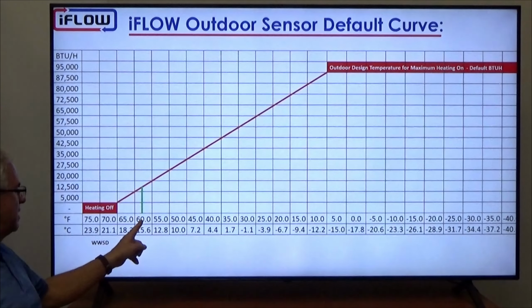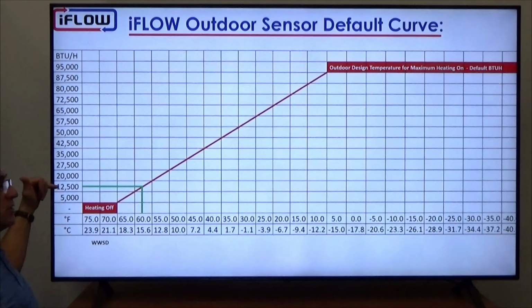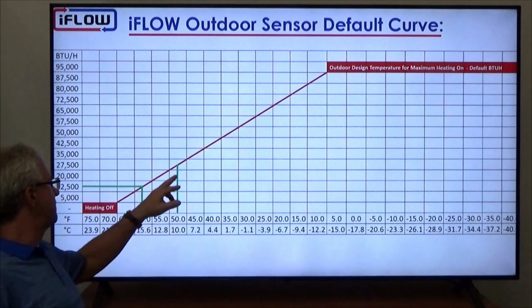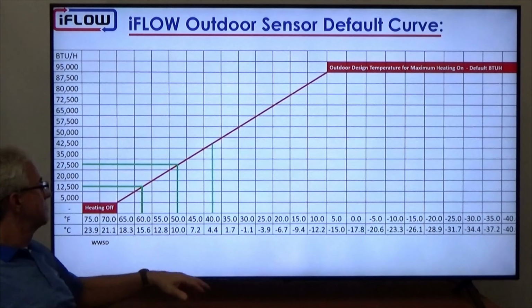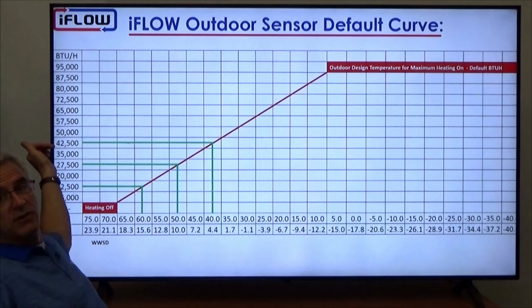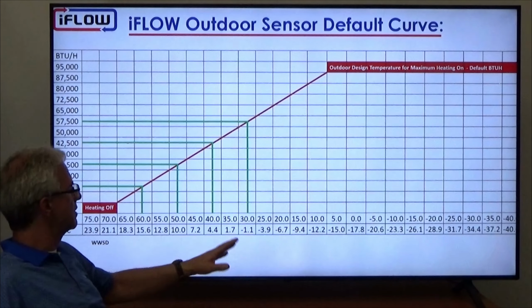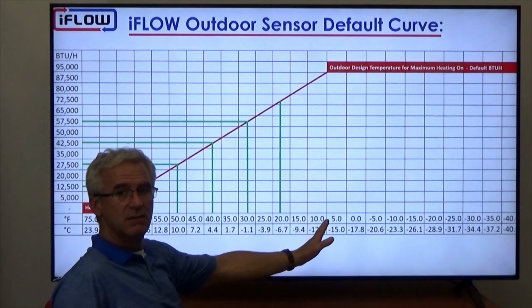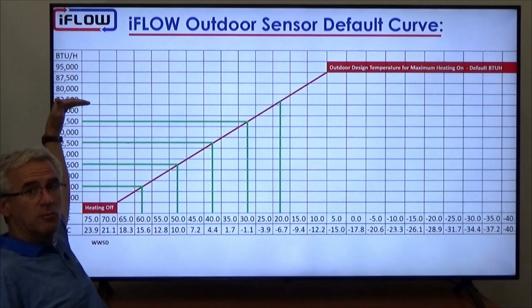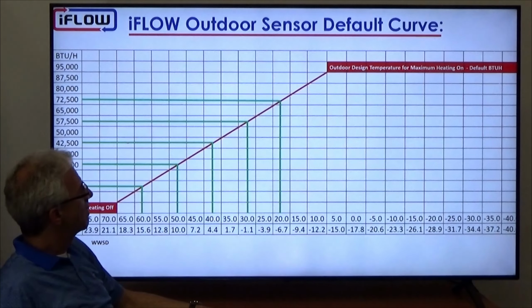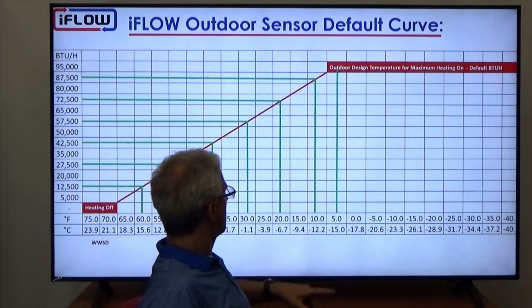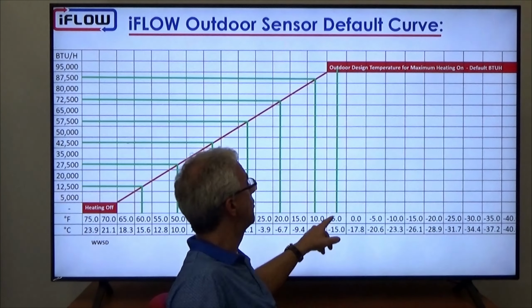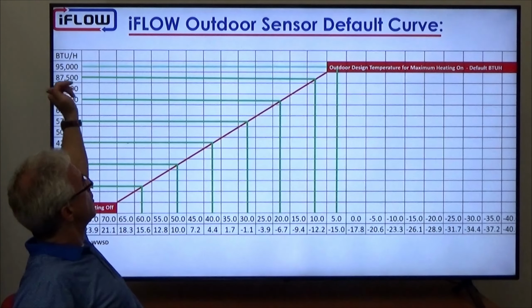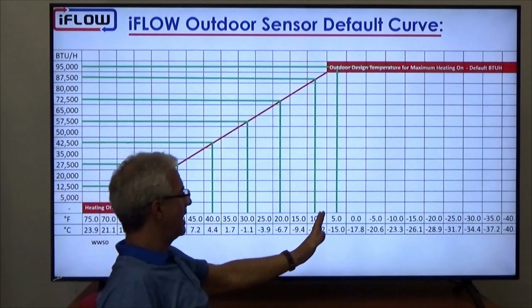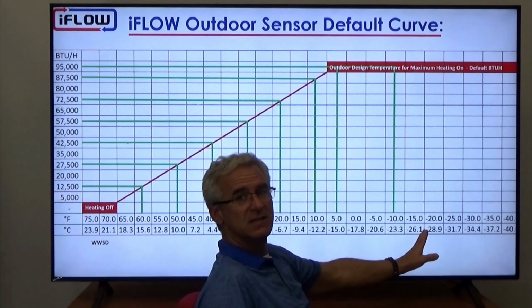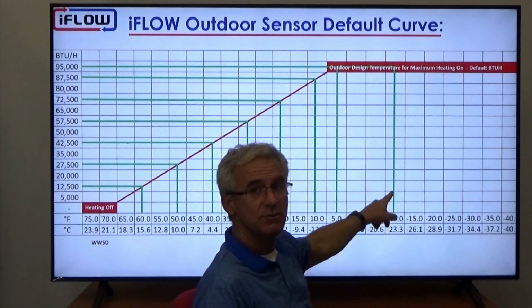For example, if it's 60 degrees outside, we're going to target and deliver over 12,500 BTUs. If it's 50, we're going to deliver 27,500. If it's 40, we're going to deliver 42,500, etc. So as it gets colder outside, we deliver consecutively more BTUs on the heating side, all the way up. Once we hit our maximum, let's say our 5, which is our outdoor design temperature for Ontario, then we will run at the 95,000 BTUs, and at any temperature colder than that, we'll also run at that 95,000 BTU level.